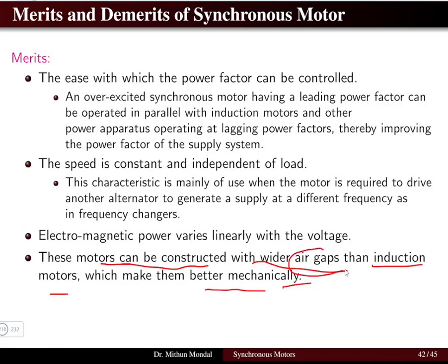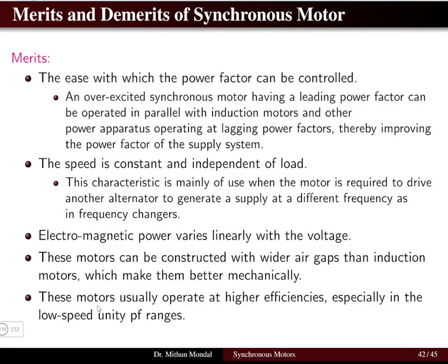These motors can be constructed with a wider air gap than induction motors, which makes them mechanically better. They also usually operate at higher efficiencies, especially in the low speed, unity power factor range, making them more efficient than induction motors under those conditions.